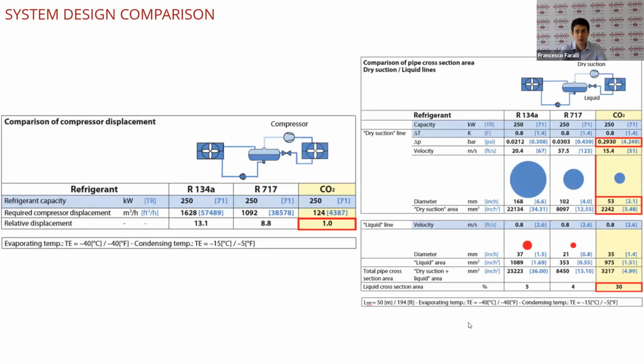Here we have some info, let's say, on the system design. CO2, when we speak about compressor displacement, is more or less 9 times smaller than ammonia. When we speak about the diameter size of the liquid line or the dry suction line, CO2 is, thanks to the higher pressure, much smaller.